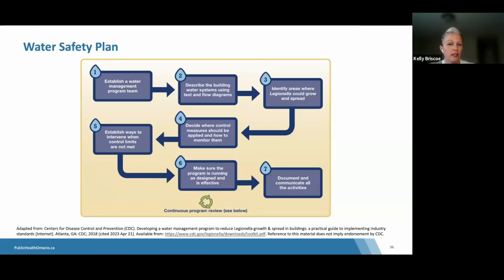You would then identify areas where Legionella can grow, and this would include a risk assessment to identify any of these locations. You would then determine where control measures should be applied and how to monitor them. So control measures can be established for each control point that may include temperature levels, disinfection levels, flushing schedules, etc. You would then establish corrective actions for each control point, so essentially a contingency response plan to respond to unexpected problems. You want to make sure the program is running as designed and it's effective, and you then want to document and communicate all aspects of the plan with employees, consultants, and residents.